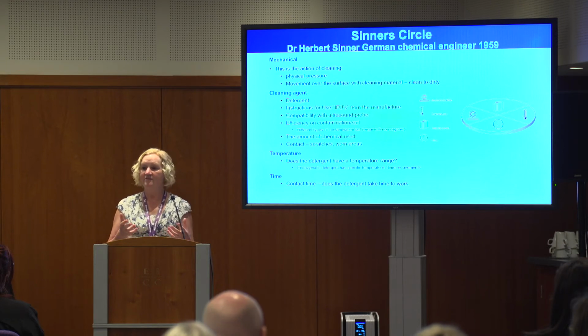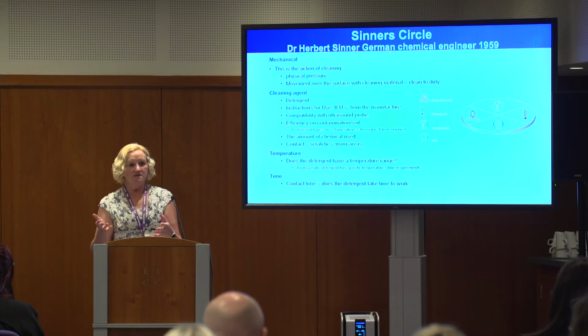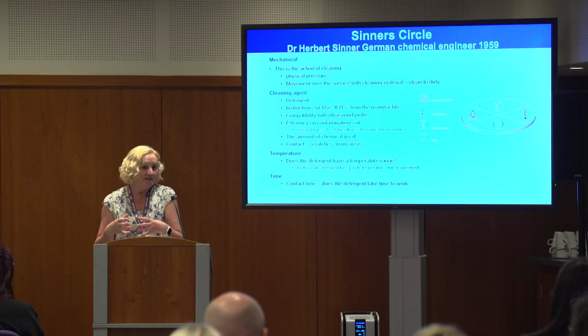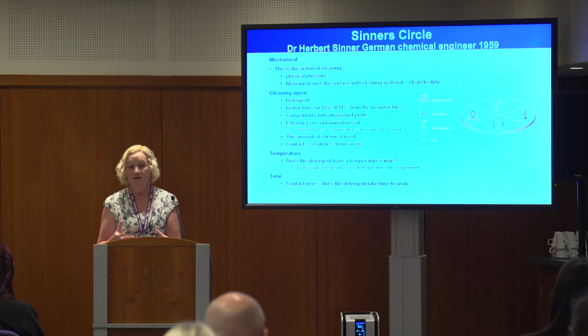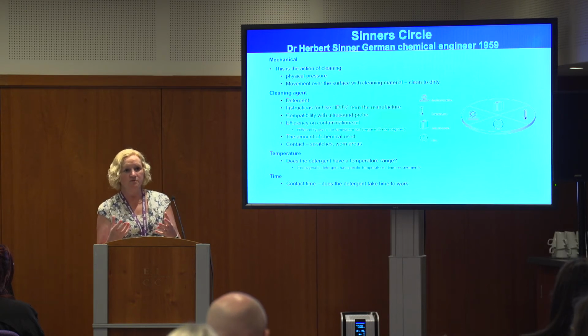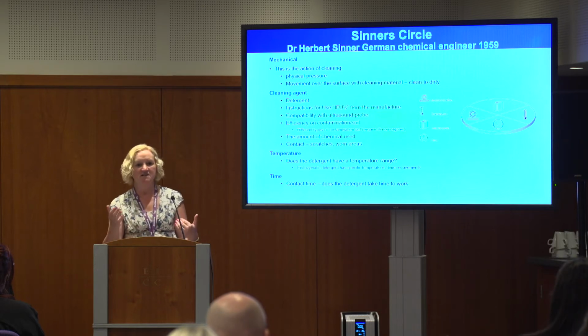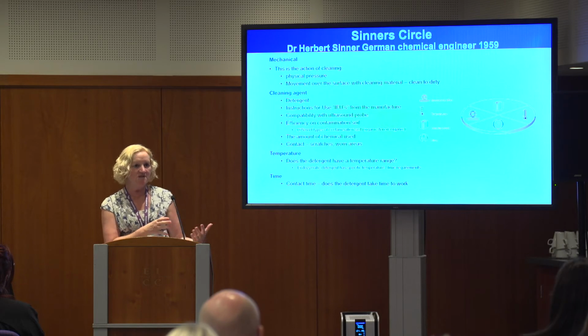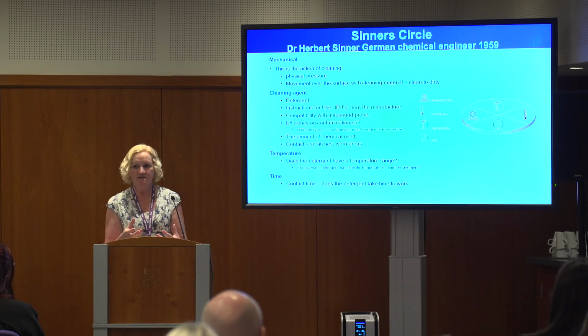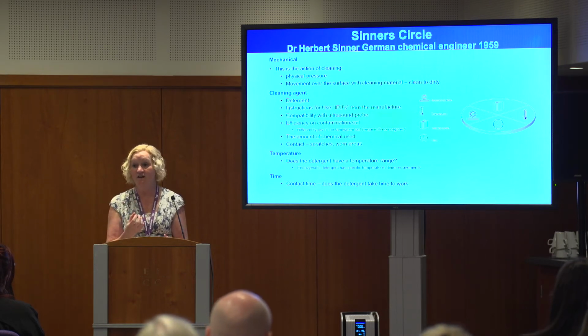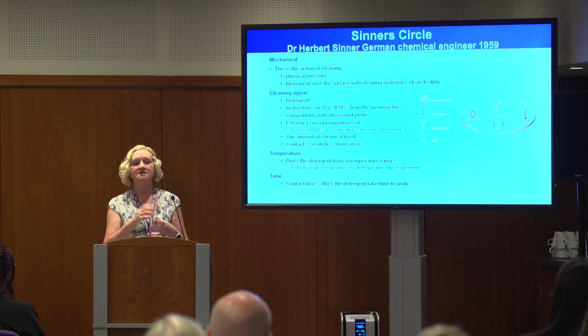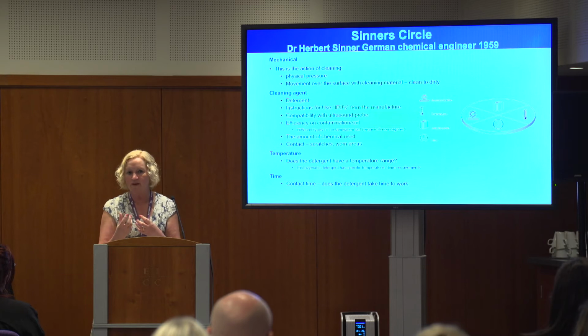Does the detergent wipe have a temperature range? If you're using it in a room, a Portakabin gets extremely hot in the summer and pretty cold in the winter. What's the temperature range? Does that affect the contact time? Most wipes are used between about 18 and 25 degrees. In the winter, for the first patient of the day, it might be colder than that. Does that mean that wipe's ineffective? In the summer, it gets very hot. Does it mean evaporation, so the concentration of the detergent is higher? Does it affect how long it has to have the contact time with the probe? These are all questions that should be resolved within your SOP and written out.